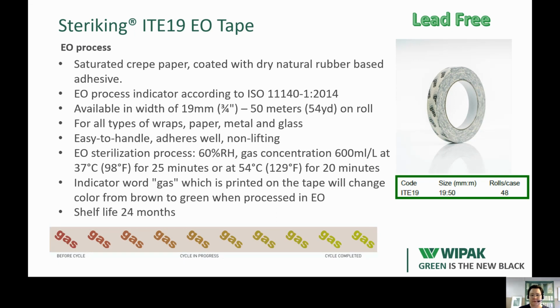Then for the ethylene oxide sterilization process, we have this EO tape that is again made from crepe paper, but this is coated with dry natural rubber-based adhesive and again contains small amounts of latex in this adhesive structure. This is printed with EO process indicator that is according to this chemical indicator standard, available in one width of 19 millimeters, having 50 meters on a roll, and it can be used for all types of wrapping materials that are used in EO sterilization, and it can also be used for metal and glass items where they want to see if the item has been processed or not. So it's easy to handle and also adheres well.